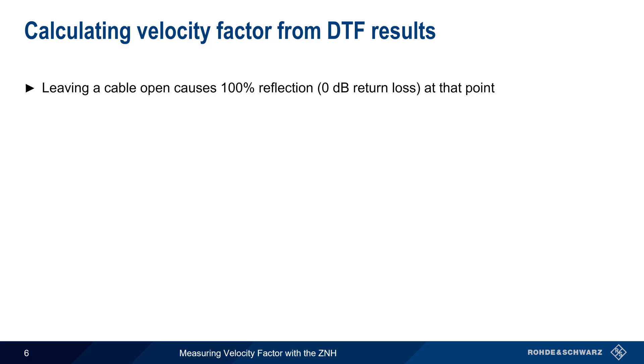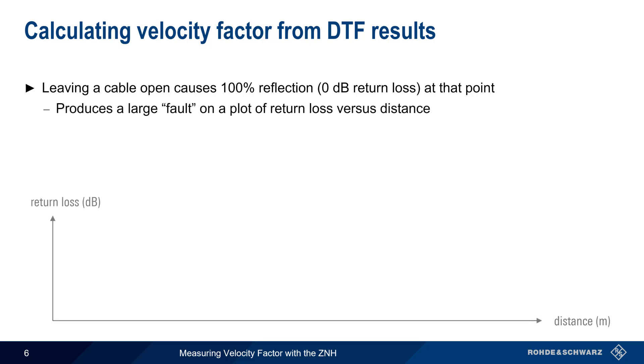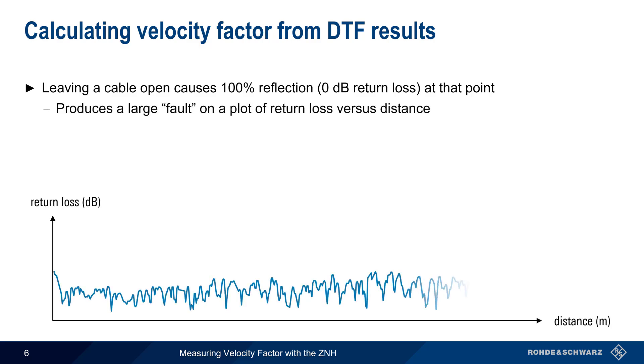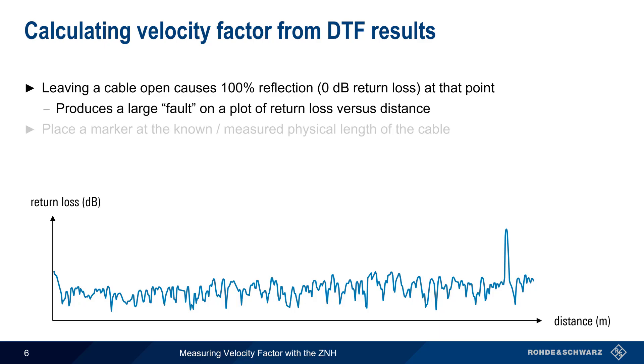When making a DTF measurement, this will produce a large fault or spike on a plot of return loss versus distance, as seen on the right side of the graph below. The velocity factor of this cable is determined by placing a marker at the known or measured physical length of the cable.